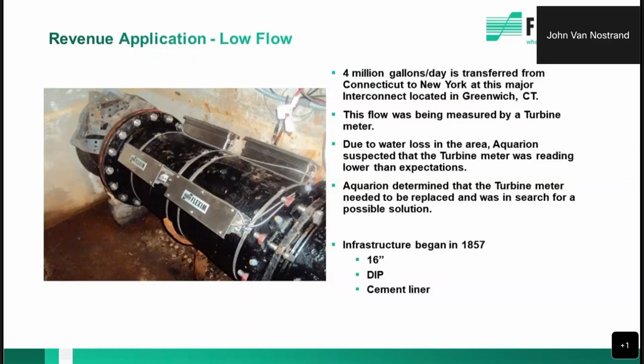This utility is in the Northeast. It's a very old infrastructure that dates back to 1857. This is an interconnect from Greenwich, Connecticut to a utility in New York State where they're selling water to them. It's a 16-inch ductile iron with cement liner, and the company was using a turbine meter for billing, and they were missing revenue during off-peak times due to low flows that the meter was not able to capture. And because of the need of greater accuracy, we actually use two sets of transducers and we're averaging them. And the customer has been extremely happy with the result, and they actually improved their revenue.